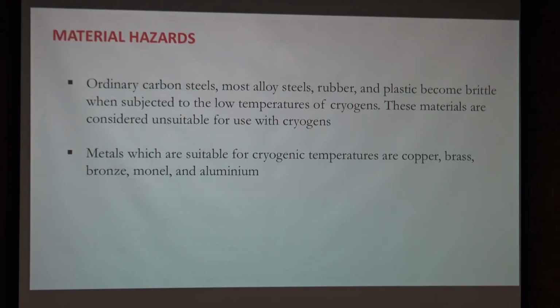Then, well, material hazards. That's a danger that is maybe not the biggest danger, but should be kept in mind. Ordinary materials, steel, definitely rubber and plastic, become brittle when subjected to low temperatures. And when their material properties change, hazards can arise, for example from using rubber pipe that freezes and then essentially shatters from cold liquids.